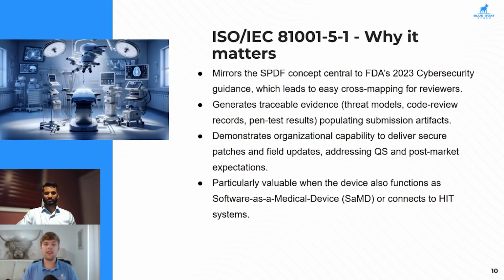Now, this is going to be particularly valuable when the device is connected into hospital infrastructure. And the reason for that is that IEC 81001-5-1 talks about medical device systems, networks, and devices themselves. It's a little bit more of a broad casted net. So we're looking at how we can handle security within the network itself. This is something that is a little bit unique that isn't necessarily addressed in some of these other standards in the level of detail that maybe it should be, since interoperability with existing healthcare delivery organization systems is critical.